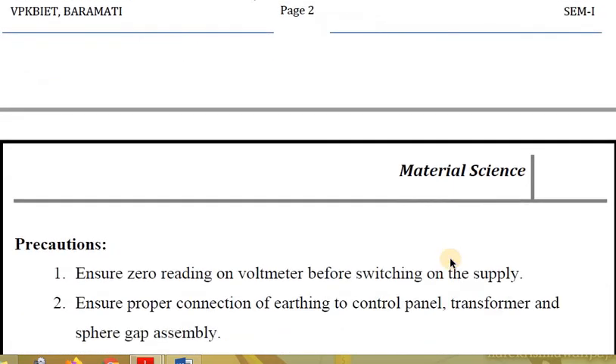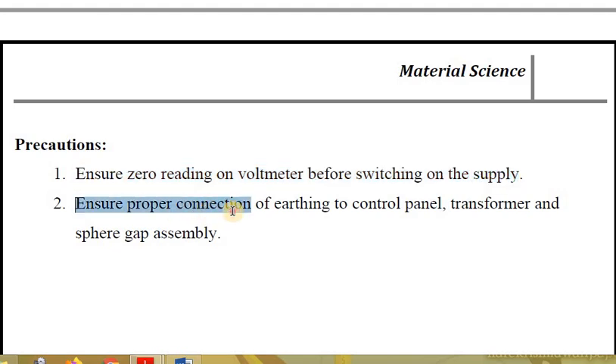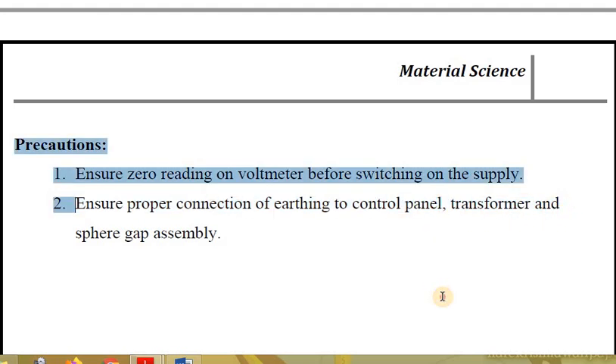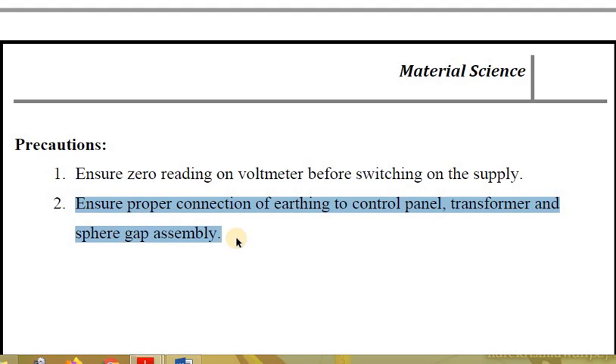The precautions to consider for this experiment: ensure the voltmeter reads zero before switching on the supply, and ensure proper connection of earthing to the panel, transformer, and sphere gap assembly. This is the complete measurement procedure for dielectric strength of gaseous insulating material, that is air. Thank you.